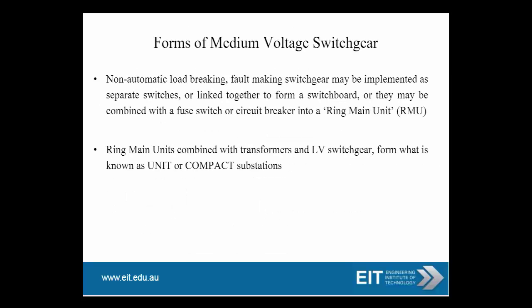For medium voltage switchgear, you have non-automatic load-breaking fault-making switches. Some of you might have seen ring main units — if you search online you will find ABB and Schneider units and different brands. These ring main units provide switching capacity for ring main circuits. Sometimes they are combined with transformers and low voltage switchgear to form compact substations. In urban areas you might see ground-mounted transformers inside a cabinet with an HV side at 11 or 22 kV, a transformer, and low voltage switchgear.